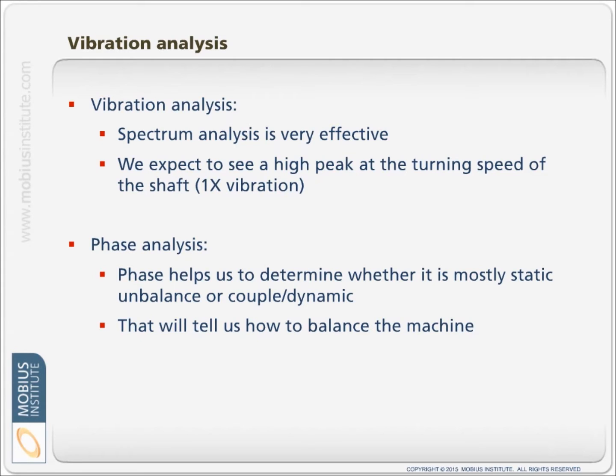But phase analysis is also very important. It helps us to determine that it is unbalanced and it helps us understand whether we've got static unbalance or dynamic unbalance, as you'll see with the animations.